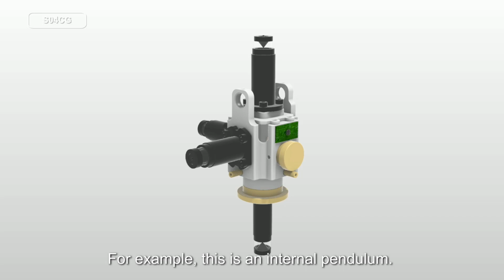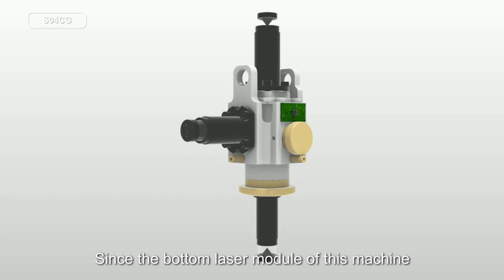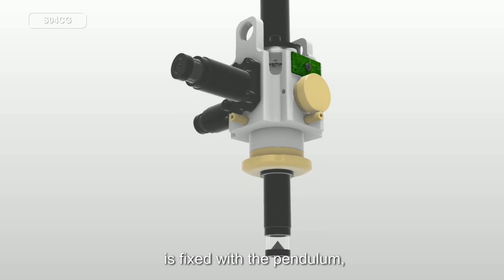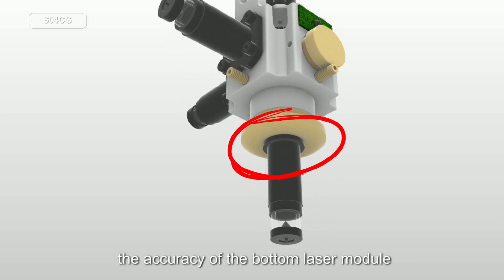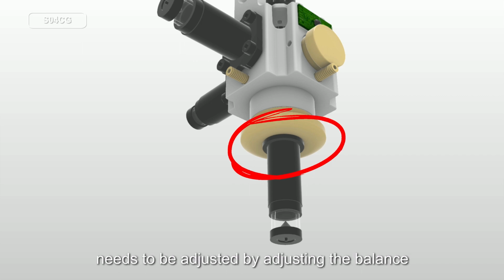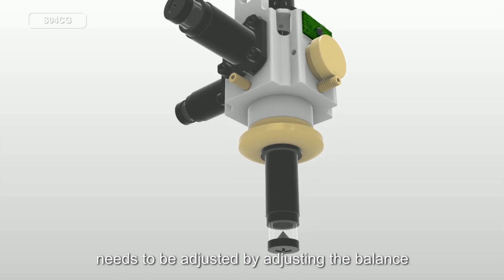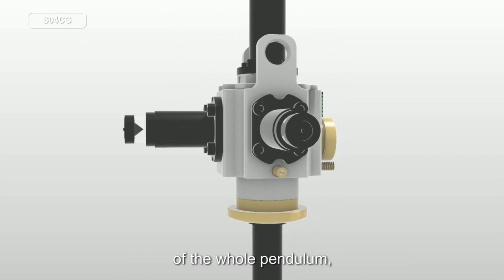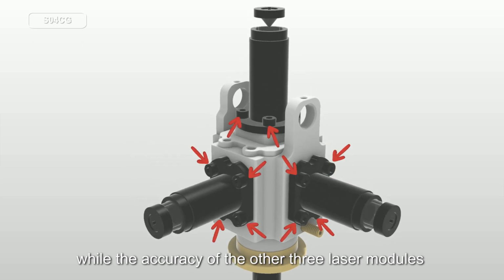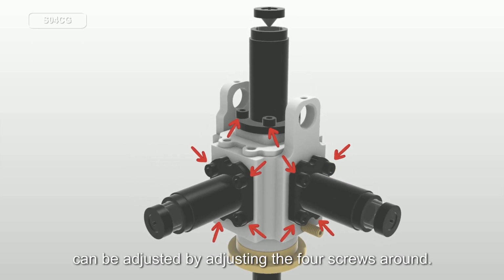For example, this is an internal pendulum. Since the bottom laser module for this machine is fixed with the pendulum, the accuracy of the bottom laser module needs to be adjusted by adjusting the balance of the whole pendulum, while the accuracy of the other three laser modules can be adjusted by adjusting the 4 screws around.